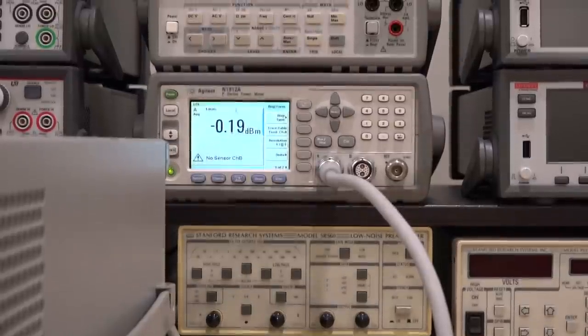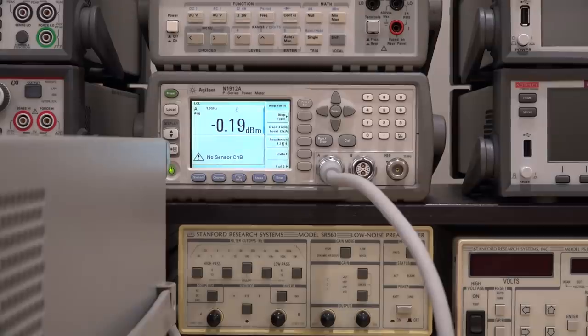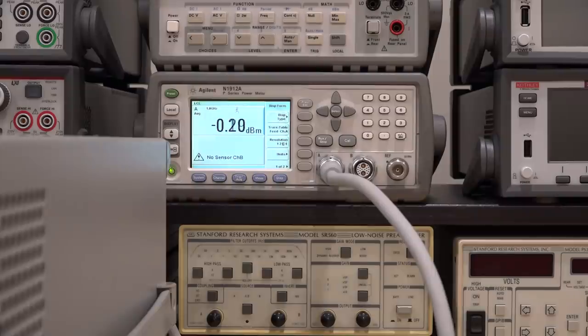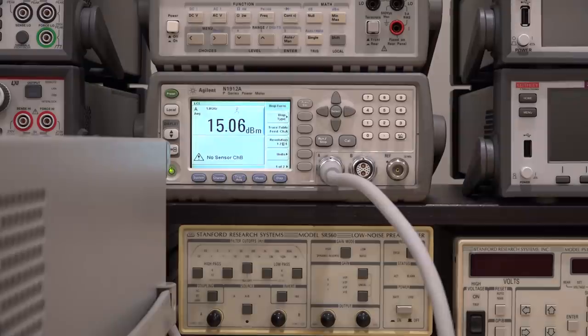That's a little bit less than 0 dBm and the reason for that is because there's some losses in the cable. But now I can go much higher power, which is quite amazing because the incident power for the S-parameter for passive lossy devices, you want to be as much as possible to improve the dynamic range of the measurement. So let's set the power. I can go up to 5 dBm. There it is. You can see it works. I can go to 10 dBm and I can even get 10 dBm. I wonder if I can go any more than that before I get unlevel. There you go. So it seems like 11 dBm still works. Can I do 15 dBm? I can even do 15 dBm at low frequencies. That's pretty amazing. So I'm quite happy with the fact that the switch is definitely working at least the module seems to be working quite nicely. So right now it's set to 15 dBm and I'm getting 15.05. So that means that there is some nonlinearity in the AGC loop inside the instrument.